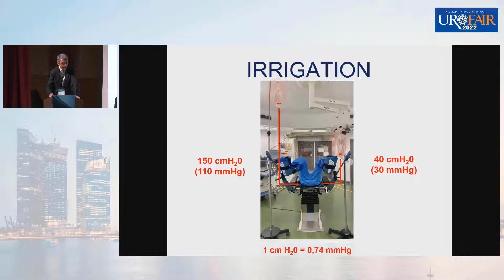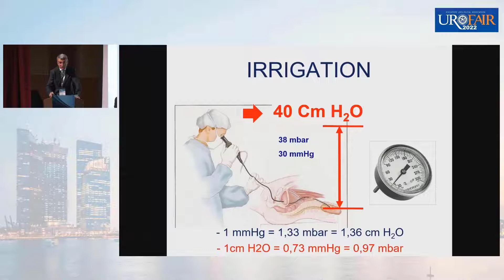What is the problem? If you have any problem in terms of outflow, the maximum pressure that you will generate in the kidney, on the left, is 150 centimeters of pressure, which is really too much for the kidney. On the other side, it will be max 40 centimeters. If you have a good outflow, then you will compensate, and then it's possible to use both. So when you are using some pressure to irrigate, be sure that you have a good outflow, just to minimize the pressure in the kidney. 40 centimeters is super safe, because the maximum you will generate would be 40 centimeters in the kidney. It's completely well balanced.